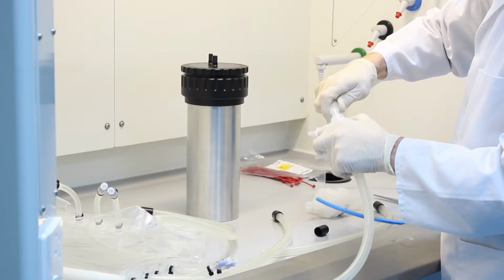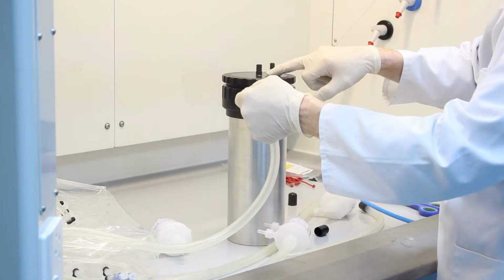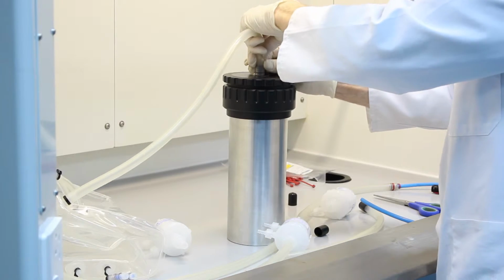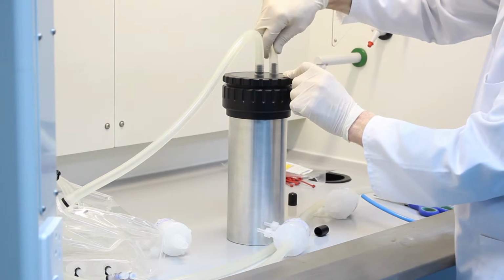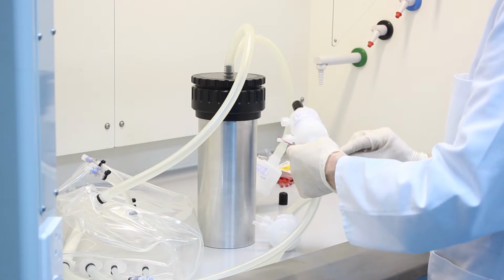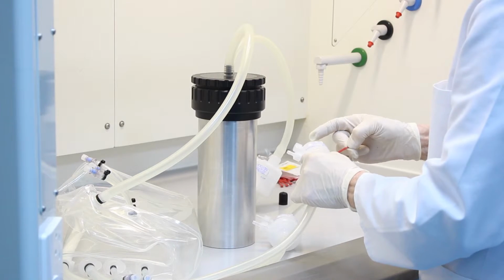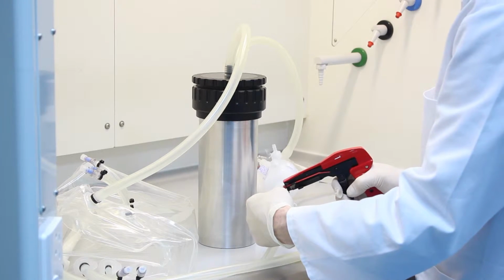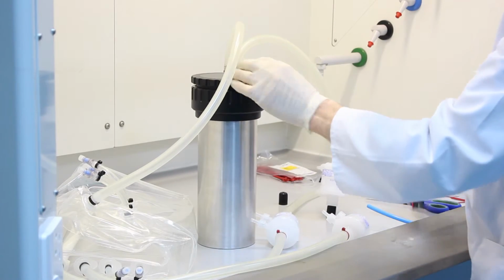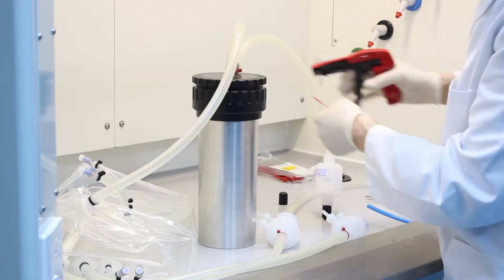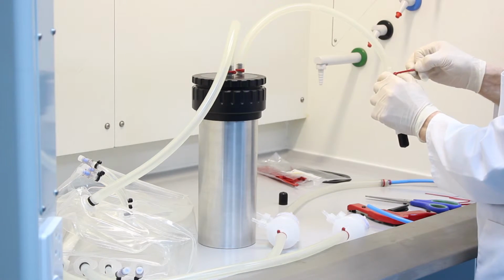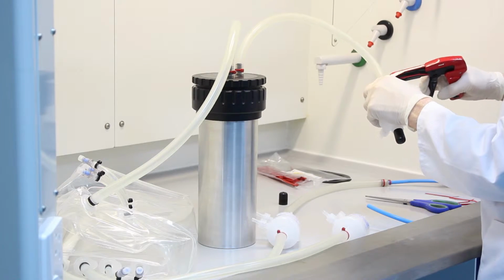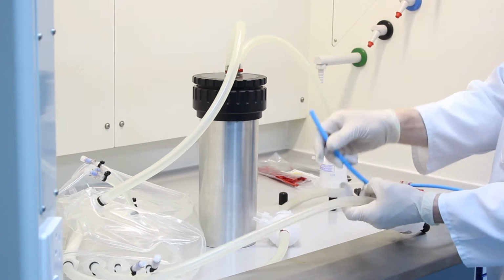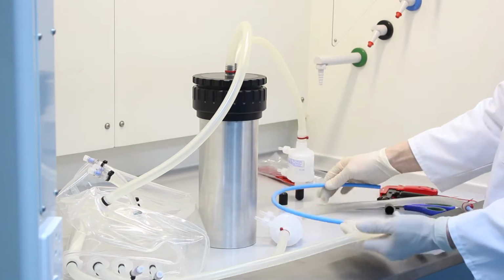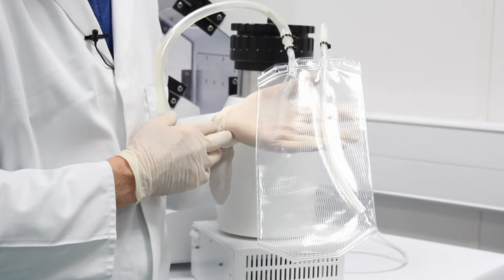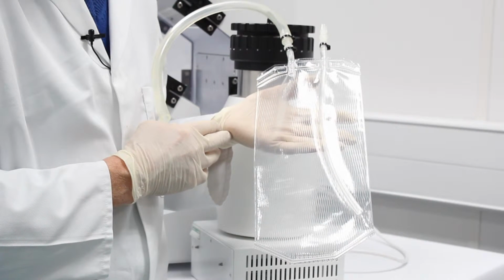Users can use 70% alcohol to maintain sterility as the attachments are made, but should users require additional sterility to avoid yeast or viral contamination, attachment to the filters may be done in a laminar flow hood as illustrated here. For further additional security, users can also attach cable ties to the tubing attachments, which is also illustrated here. A highly efficient condenser system is incorporated for the removal of moisture from the exhaust line via a microbiological filter to prevent contamination. Optionally, gamma irradiated single-use condenser liners are also available to enable ease of use as well as fast setup and turnaround times.